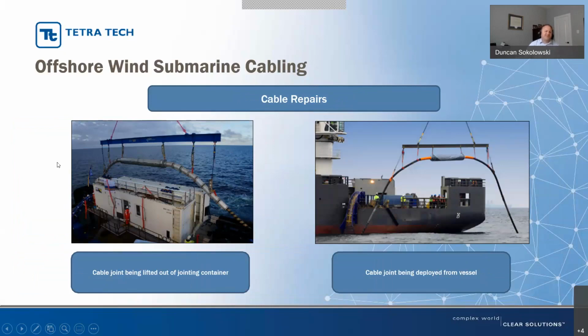A necessary part of the cable industry is doing joints, whether it's for repairing a cable in the event of a fault, or during installation. For example, with a long export cable, no cable ship will be able to take the entire length of cable in one go. It might have to go and refill, as it were, which would necessitate doing an offshore joint.